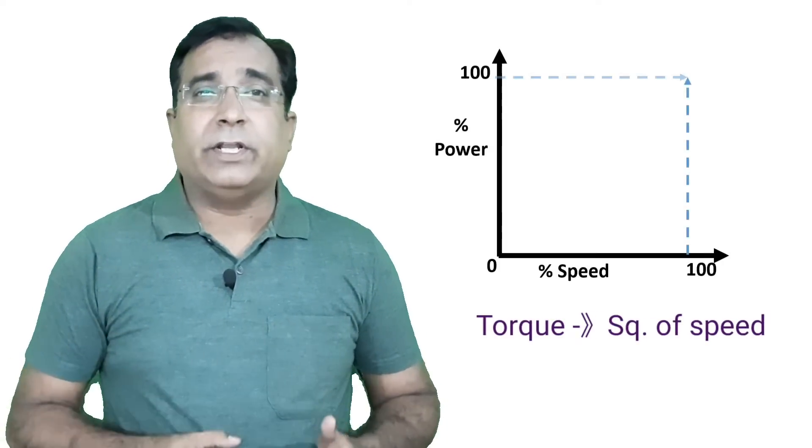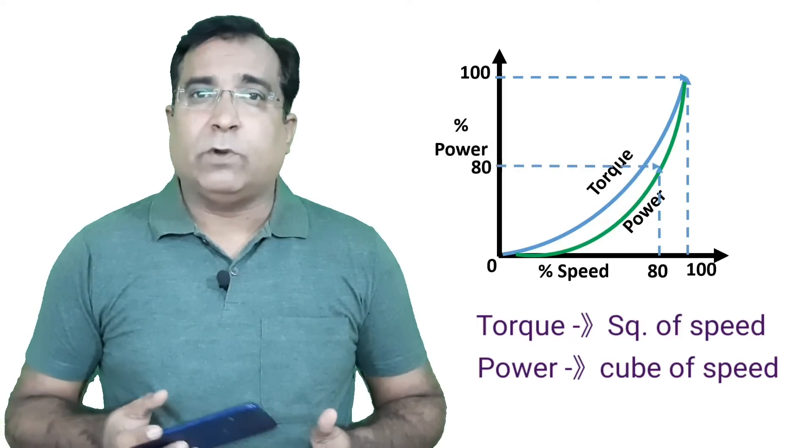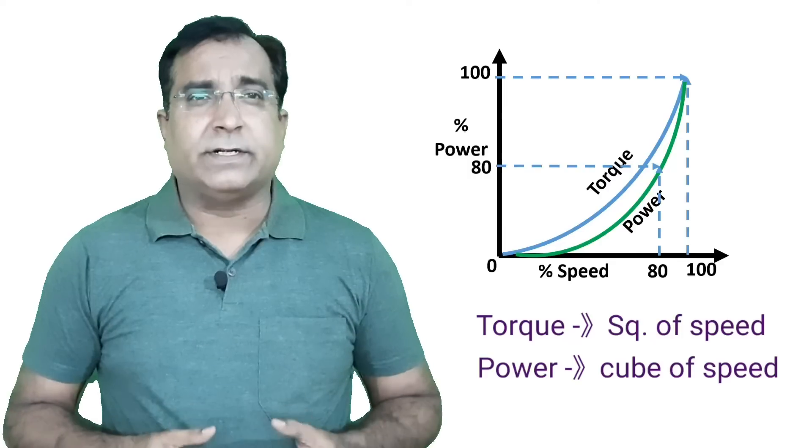Here, required torque is varied according to the square of speed and power varies according to the cube of speed. This category includes centrifugal, axial pumps, fans, blowers, many mixers and agitators.